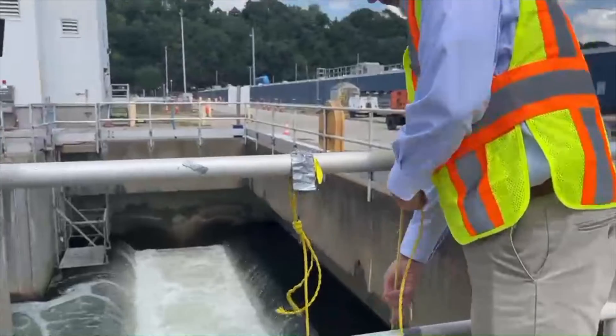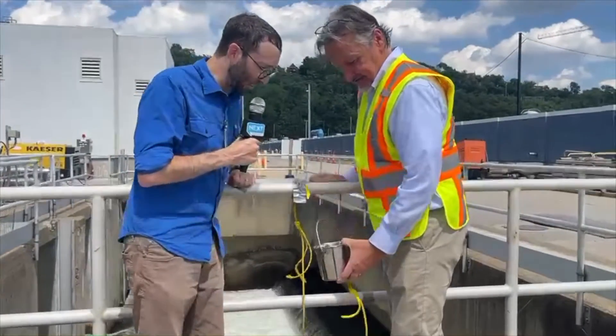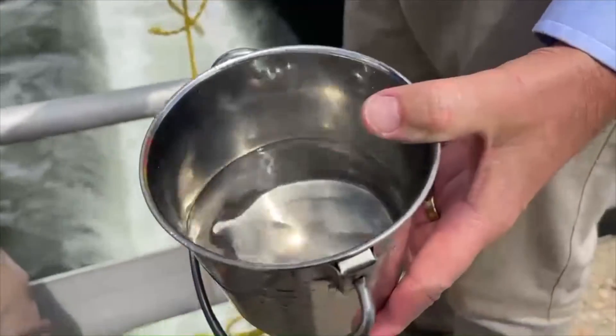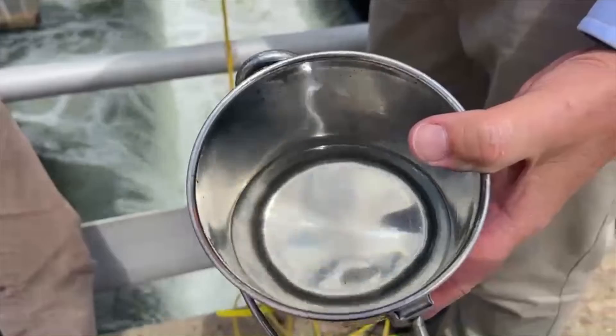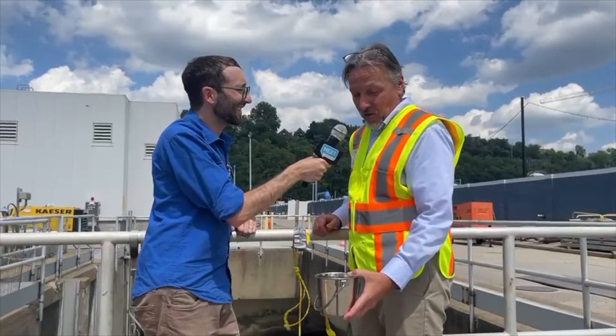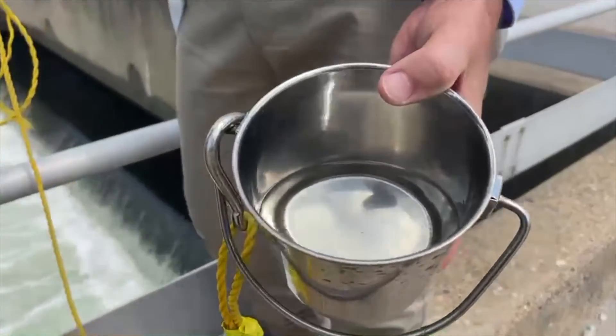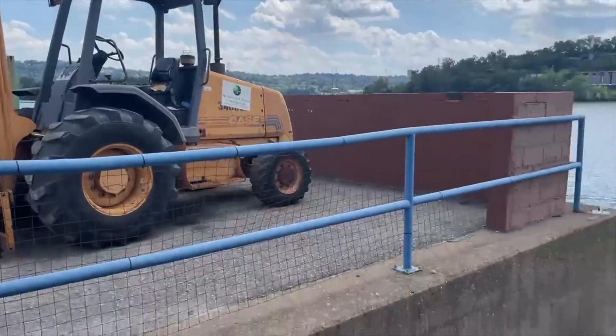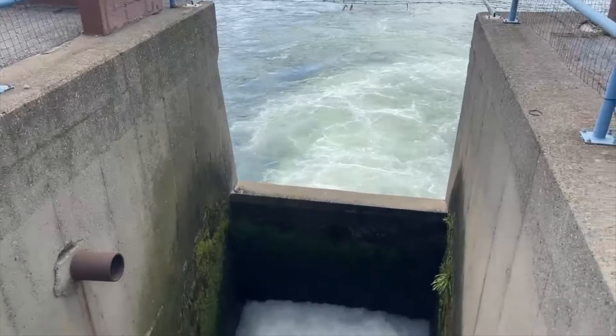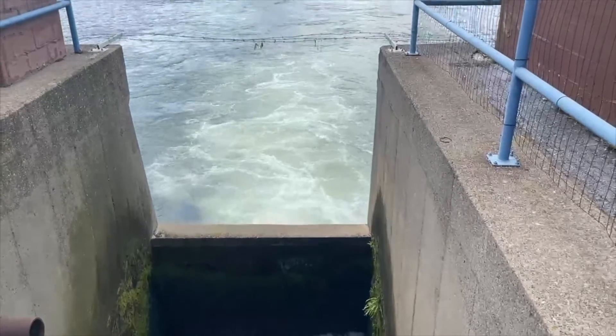So we've got a bucket of water coming out from the discharge area here. Wow — this looks a lot different than it did, gosh, probably just a few hours ago. This really looks like crystal clear water. Yep — so that's nine to twelve hours after that very polluted wastewater made its way into the wet well, after all the bugs did what they needed to do. We settled out all the activated sludge and the majority of the pollution out of the wastewater. We threw some chlorine in there to kill as many of the bad bugs as we can, then put one more chemical to get rid of some excess chlorine, and that's what you have. The Ohio River is a massive body of water, so we really are a small contribution to the water quality in the region. During wet weather days, those overflows — that's what the billion dollar Clean Water Program is in place for: to deal with overflows that occur during rain events.